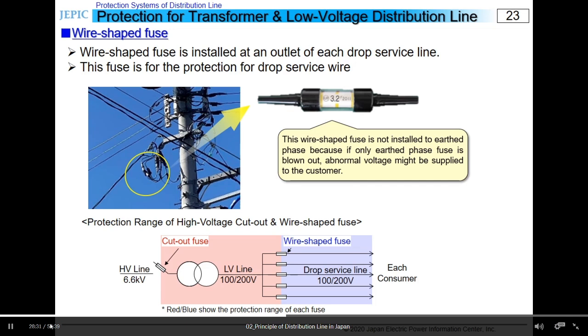The protection range of high voltage cutout fuse and wire-shaped fuse is as shown in the figure. Transformers and low voltage distribution lines are protected by high voltage cutout fuse, and drop service lines are protected by wire-shaped fuse.